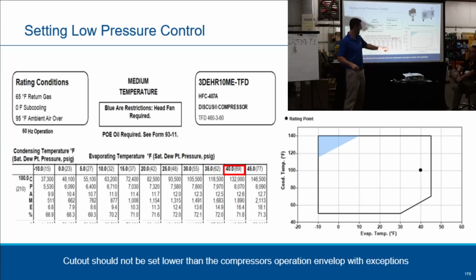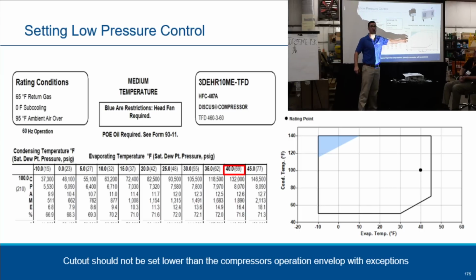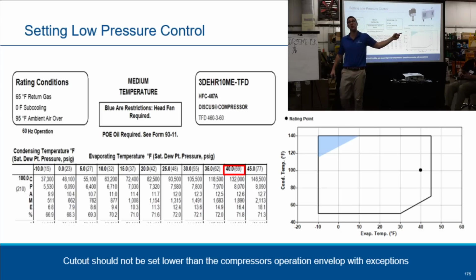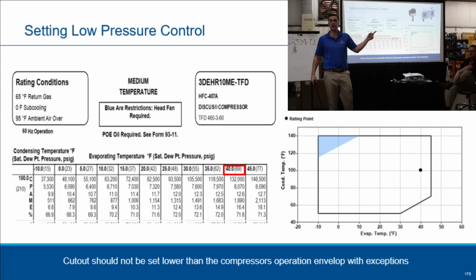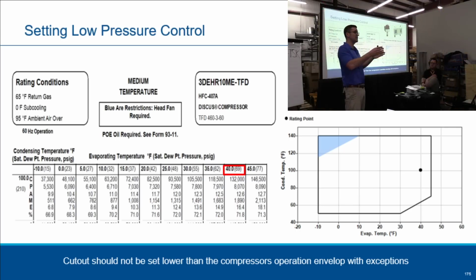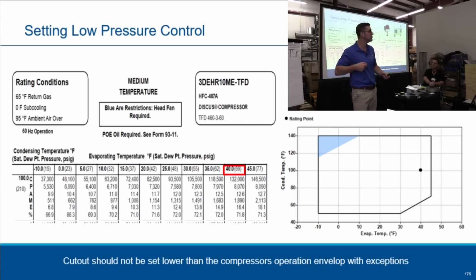So if you pump down a compressor this far, you should pull out all that refrigerant out of that evaporator. That's the whole purpose of a pump down, right? So if you run it and run it and run it, and it pumps down, and all of a sudden it starts to rise, you could have bad valves. Another thing is if it runs and runs and doesn't make it all the way down here, once again, it could be something wrong with the valves. So you don't really have to get in and start doing these valve tests, because we don't recommend you pulling our compressors in a deep vacuum and then doing a hold test.